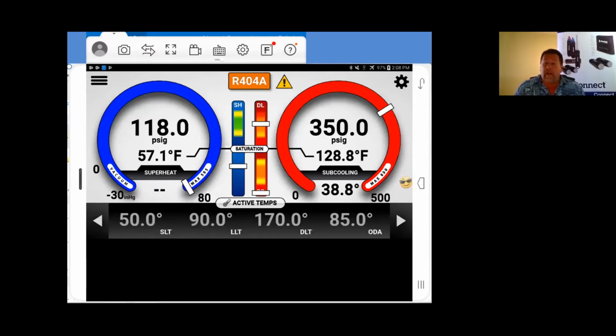And depending upon the situation, the best place to put in your supply temperature probe is probably on the first available register, say in the laundry room or the kitchen. That's where you've got really good supply air coming out. And those are just simply slid in to the duct. You can use several different methods. I've seen all kinds of different methods. Some guys use a magnet taped to it. You can use this type of an office clip. I've seen that used before. And pretty much any way you want to do it, as long as it's in that line of airflow.